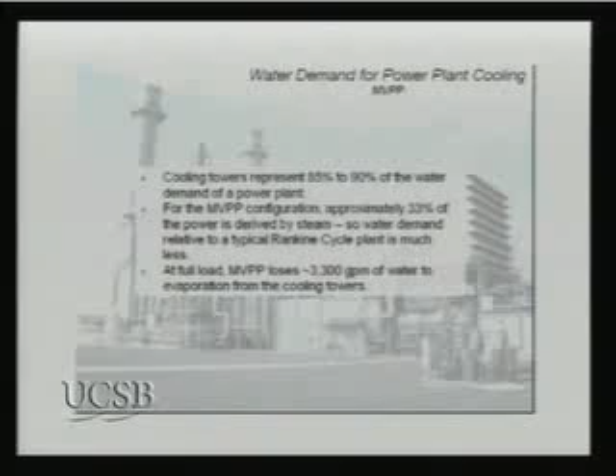The cooling towers represent 85 to 95% of the water use. This plant uses a third of the water of a comparably sized Rankine cycle plant for cooling, because only a third of the megawatts are driven by steam turbine. So you have a third of the water demand. The average water demand is about 3,300 gallons a minute, which can get up to almost 5,000 gallons a minute in the summertime when it's really hot.